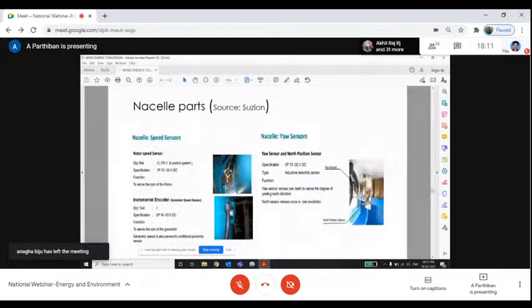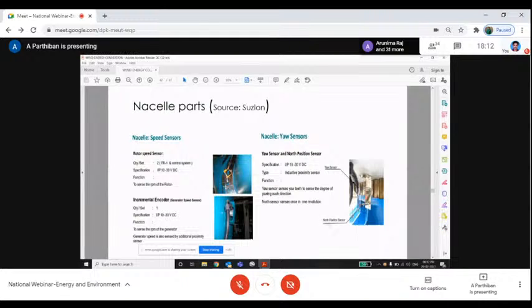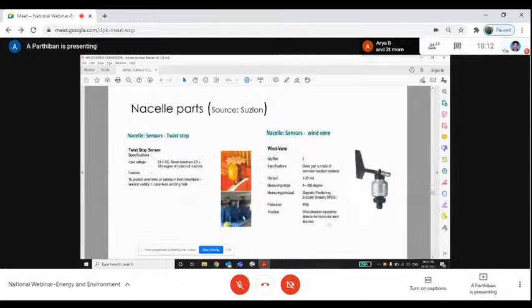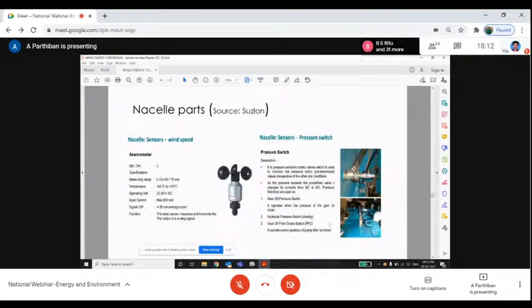And these are different sensors: speed sensor and yaw sensors. Once the nacelle has rotated 360 degrees, it should rotate back, because all the cables from the top of the nacelle come down to the control panels, so the cables should not twist. For that purpose, once the nacelle has completed its 360 degrees, it will rotate back to 0 degrees. For that, the north direction is kept as a reference, and for that only the north position sensor is used. And this is a typical wind vane, for measuring wind direction and wind speed, because based on the wind direction only, the yawing will happen.